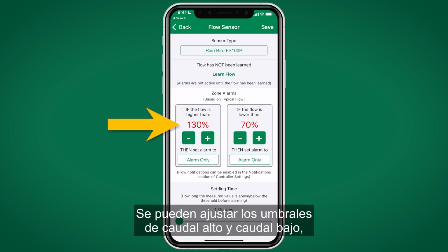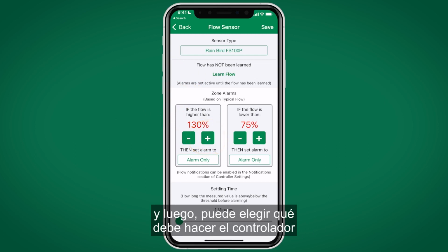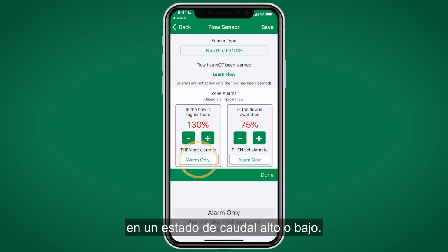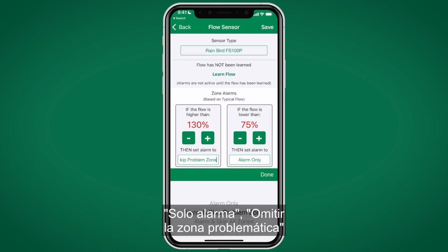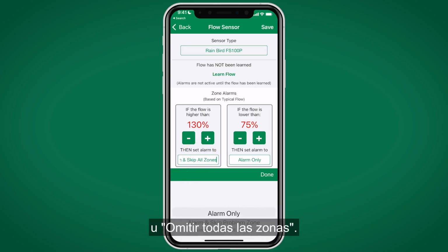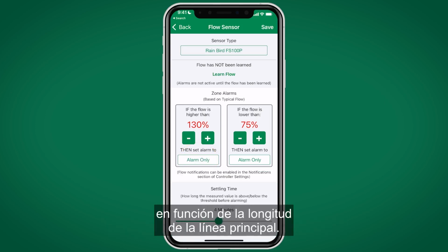The thresholds for high flow and low flow can be adjusted, and then you can choose what the controller should do in a high flow or low flow state: alarm only, skip the problem zone, or skip all zones. Settling time can be adjusted depending on the length of the main line.